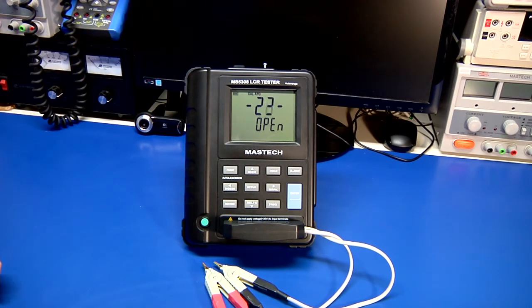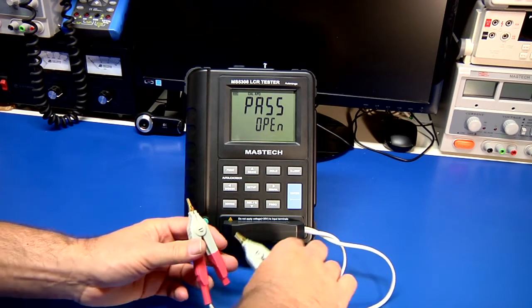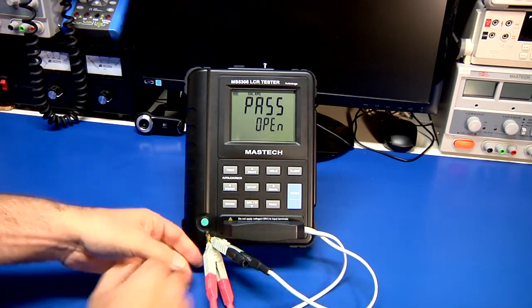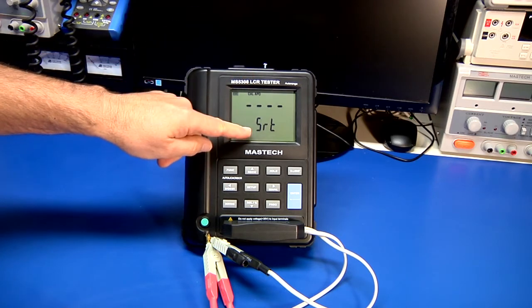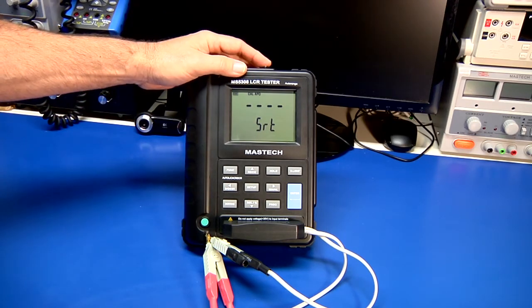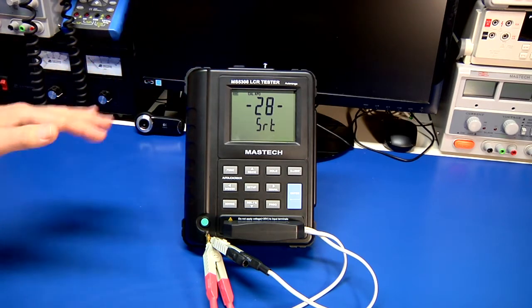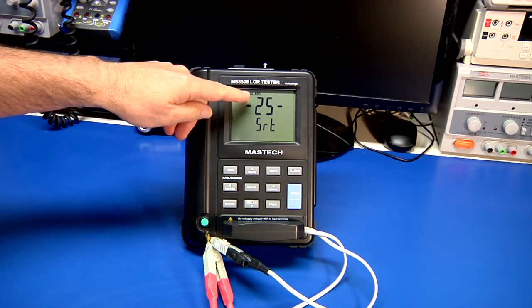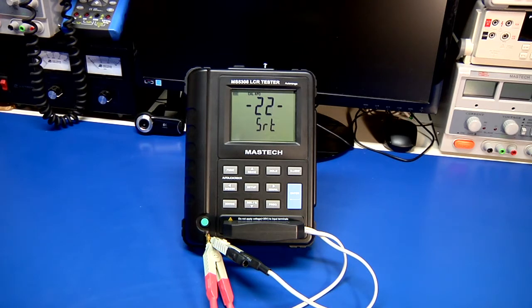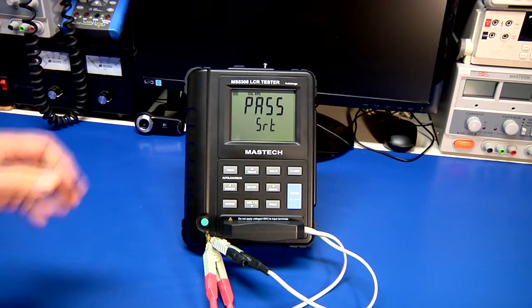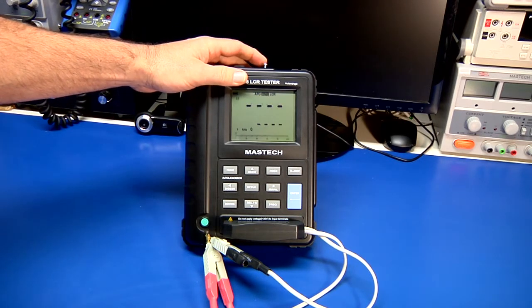Again, I'll edit this out so you're not seeing the whole thing. So here we're approaching the 0, and we get a pass, which means it's done the calibration for the leads being open. The next operation is to short the leads together. You press the button again, and it'll go into short mode. It's the same process. Press the button again, and it'll do a 30-second countdown as it's doing its calibration. It also has a little cal indicator up here while it's doing that process. And we're down to the 2 seconds, and we get a pass, and now the system's calibrated. Press it one more time, and it takes it out of calibration, and you're now back in the normal mode of operation.